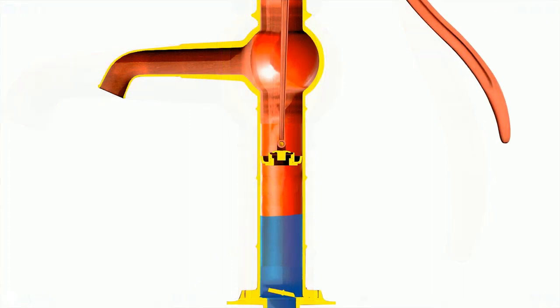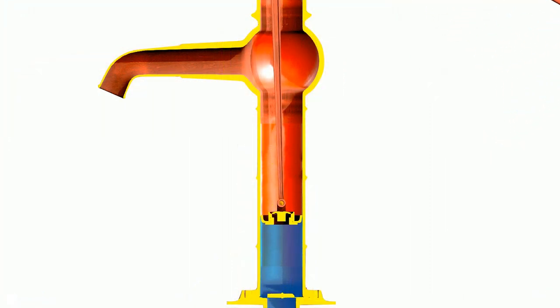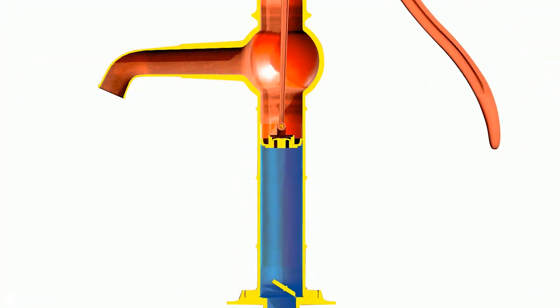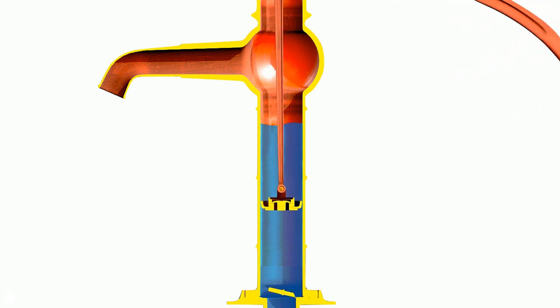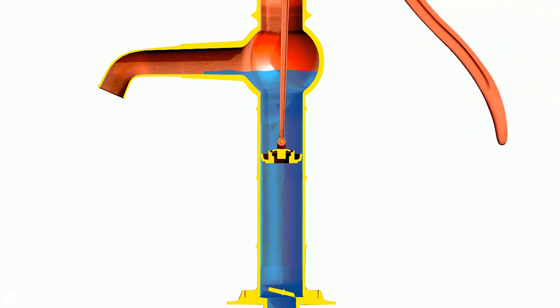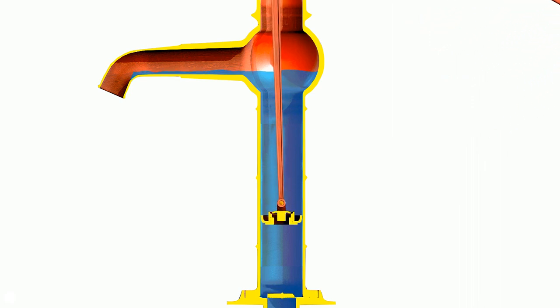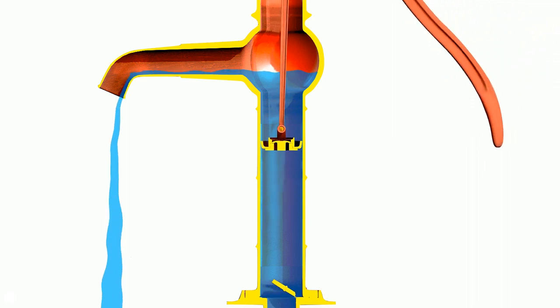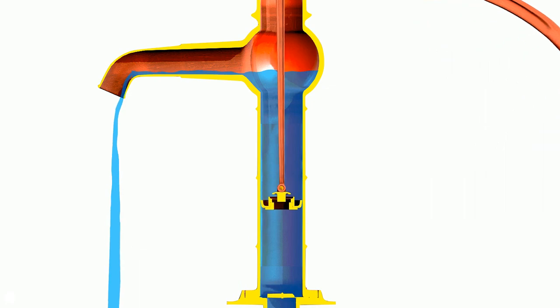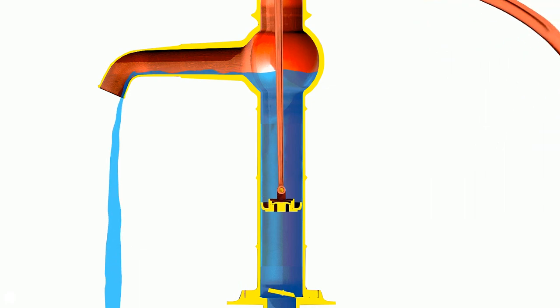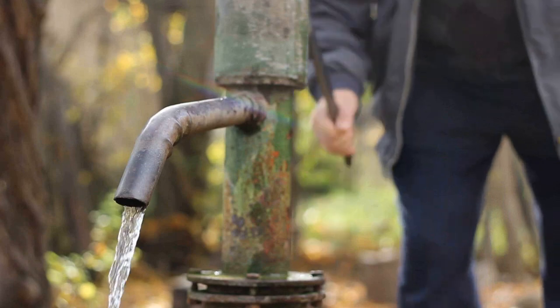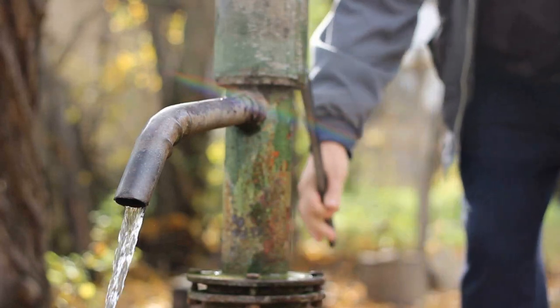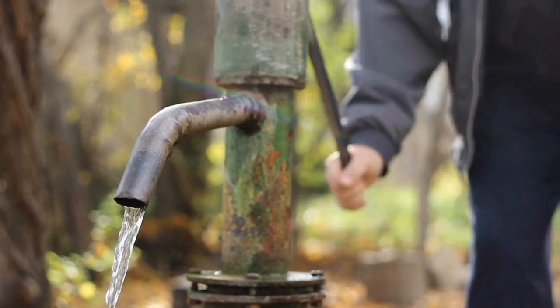What we're doing is controlling the flow through the pump using a series of one-way valves or check valves, non-return valves, whatever you want to call them. And that's allowing us to displace the fluid from one area to another. That is to say from the lower side of the piston to the top side of the piston. For this reason, this is a type of positive displacement pump.